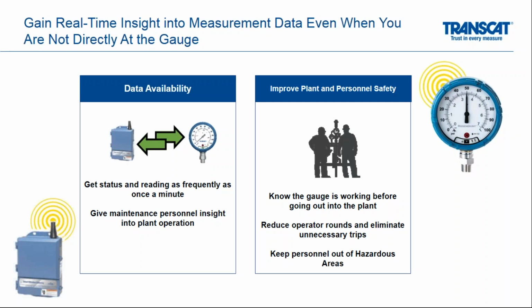I mentioned the data availability. With the wireless pressure gauge, up to every minute, that information can be sent over. So every minute, there might be a new pressure. Chances are you're not looking at these gauges every minute, but it's another great indication to know that the gauge is working properly. And then you can give maintenance personnel insight into the plant operation. It can also actually improve plant safety. What you can do with wireless communication is many operators and workers can actually know about the gauge before they go and do rounds. And if something is happening to one of those gauges, they can prepare themselves. They can equip themselves properly before they go out in the field. And if nothing is happening with those gauges, they don't need to put themselves at risk and go into what could be a hazardous location in the plant.